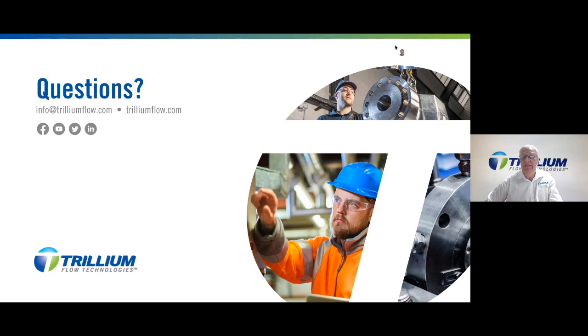One of the early pictures that we saw, as Graham pointed out, is an application where the customer expressed that the fluid was clean, and they basically came to us and said, your valve's leaking. It was only when they then showed us the photos of the valve that we could establish that they had a significant amount of carryover from the sand that is present in the fluid. So not always known when the process starts up. Some processes can have carryover, which is unexpected.